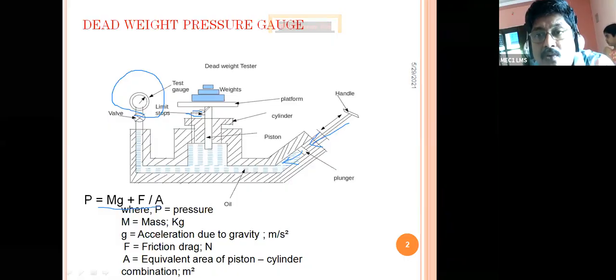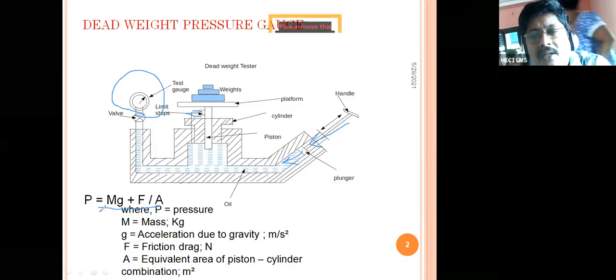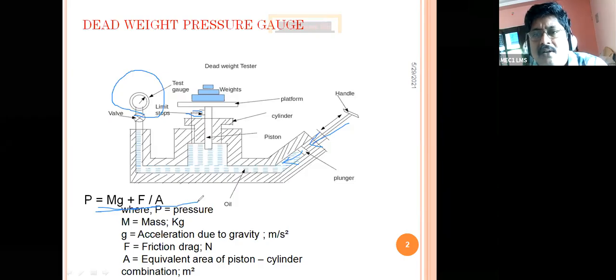At that point you note down the reading of the test gauge. Whatever reading you got, and whatever theoretical reading you calculated, these two should coincide. That is the calibration procedure. Then we can say the gauge is working properly. If there is an error, you have to adjust it so that it gives the correct reading, and then the calibration process is complete.